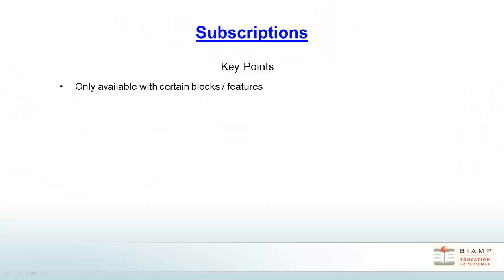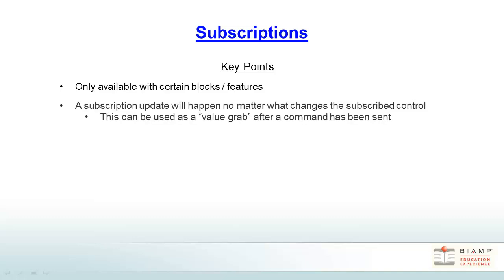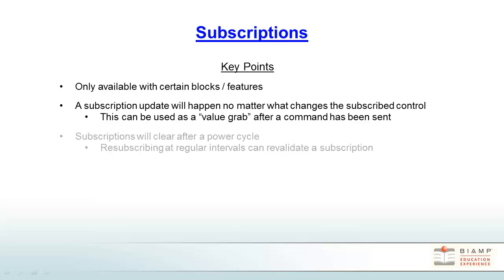In the Tesira Text Protocol, you can create subscriptions to DSP blocks that can provide unsolicited feedback to a third-party control system. Subscriptions are only available with certain blocks and features. A subscription update will happen no matter what changes the subscribed control. This can be used as a value grab after a command has been sent.